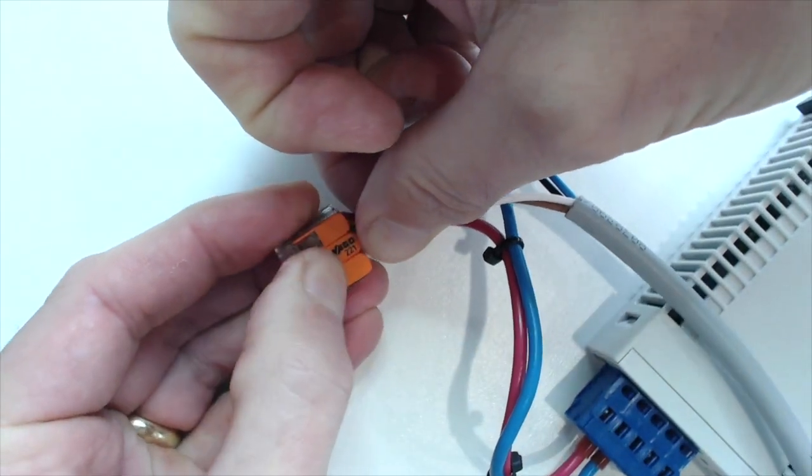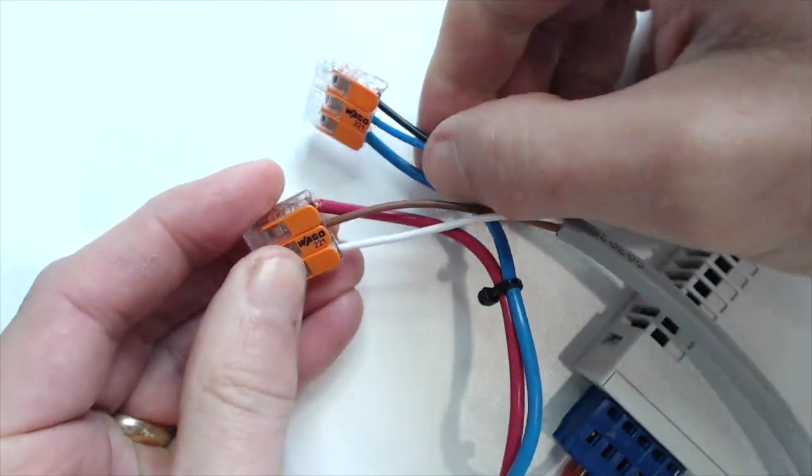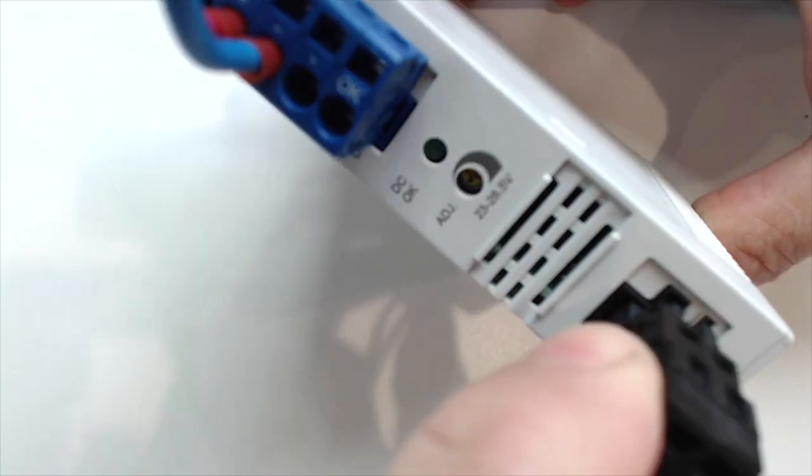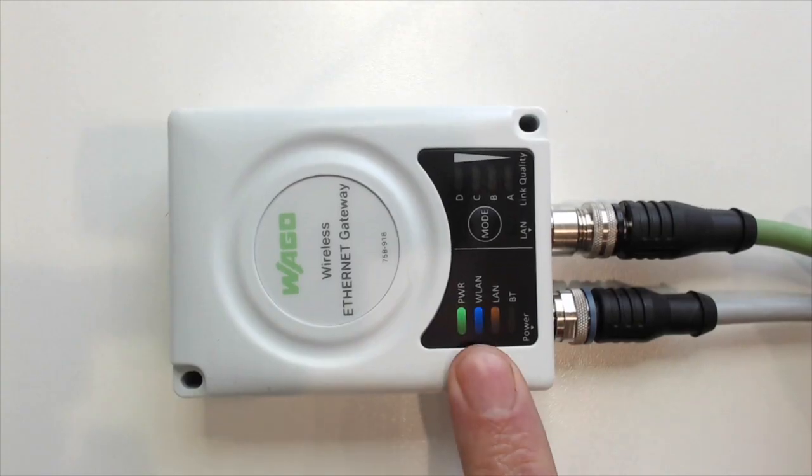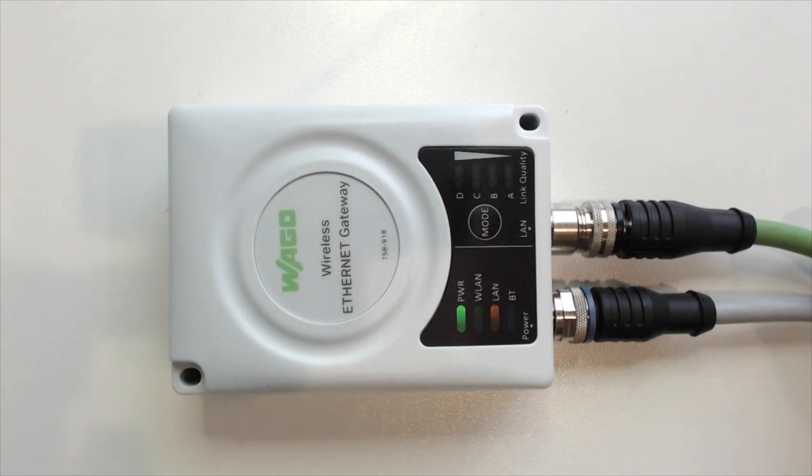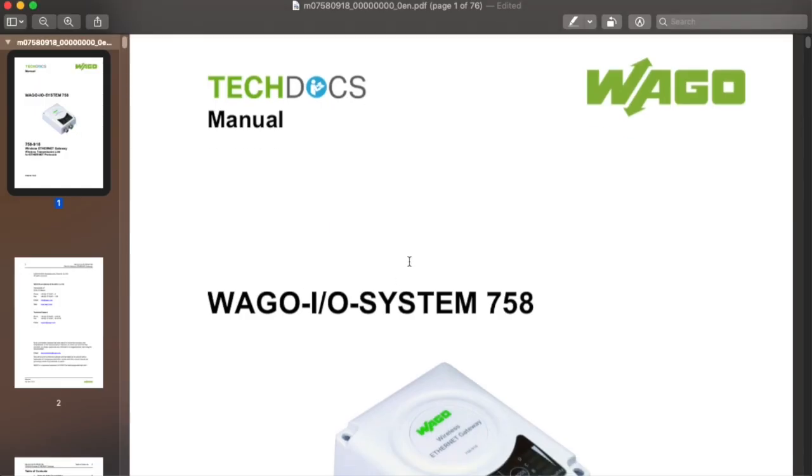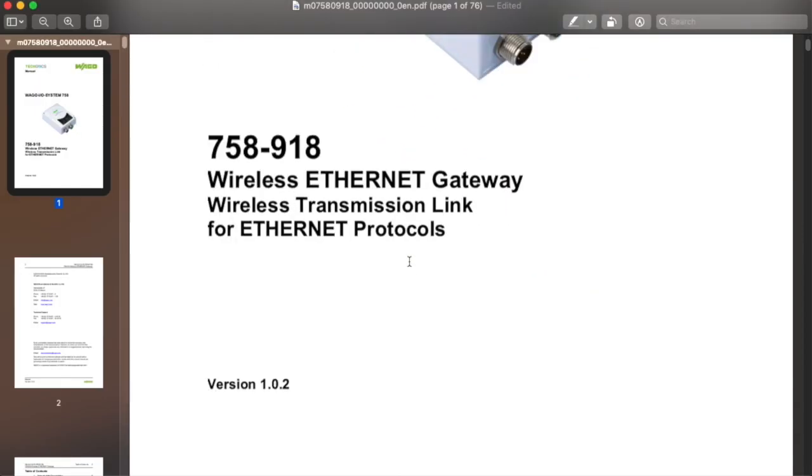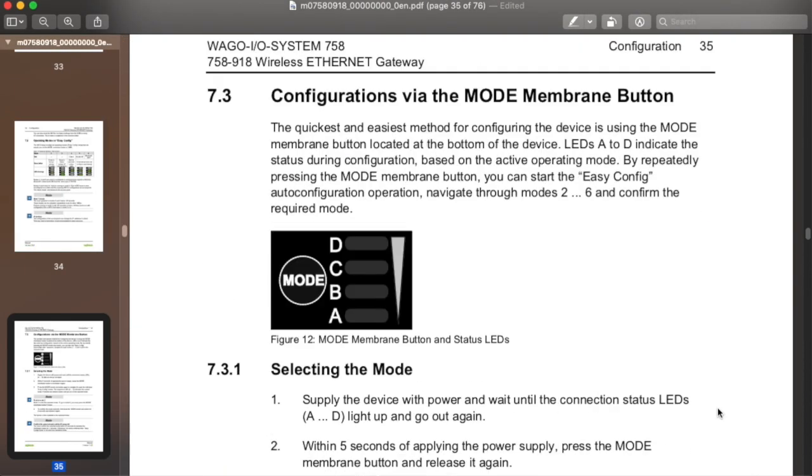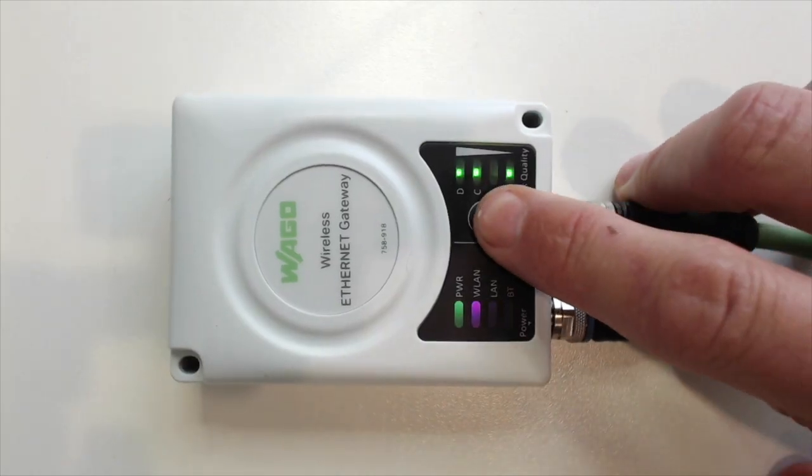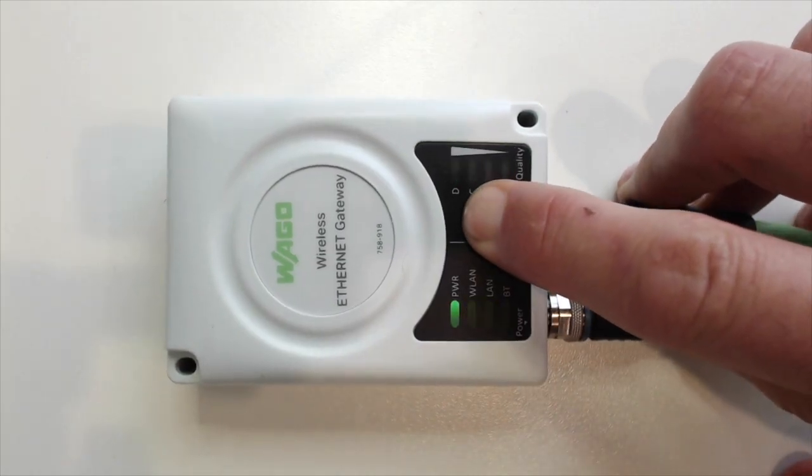There's a very easy way to set the device back to factory defaults. If you consult the manual, there's a whole section on performing the procedure, and I'm going to walk you through it here. Down on section 7.3.2, you can see if you turn the device on and then hold the mode button for 10 seconds, that will set the device back to its factory default.